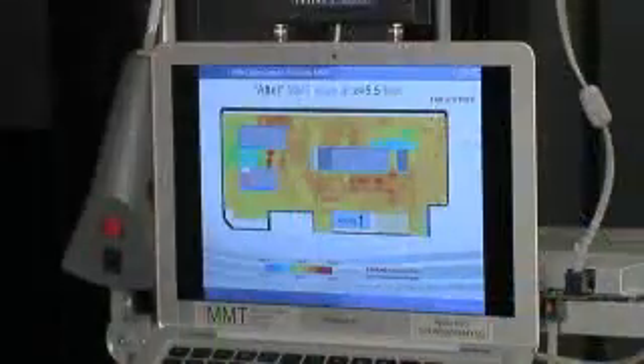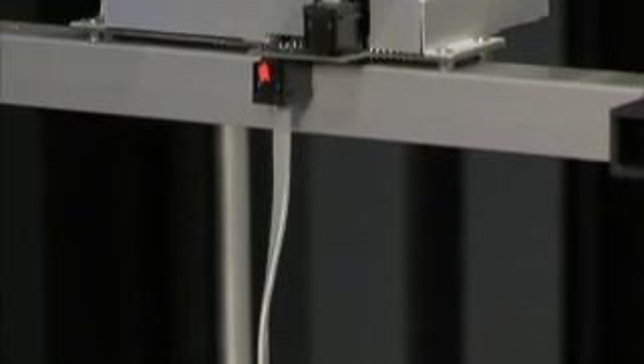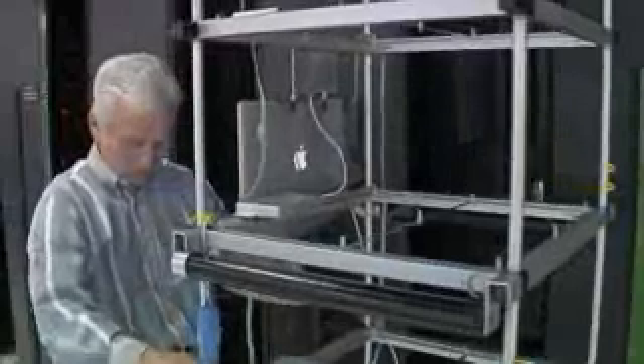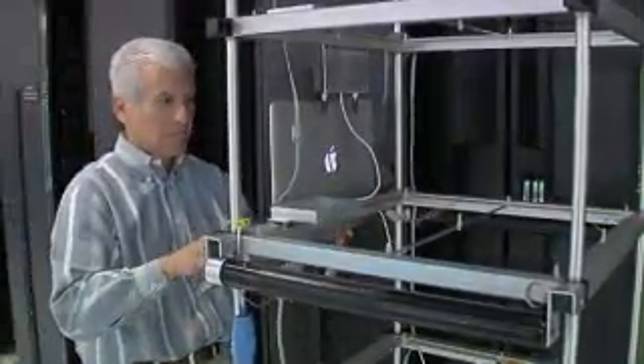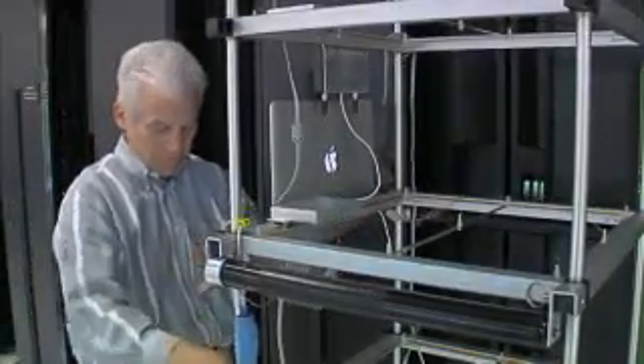The first step is really to determine where the problem areas are in the data center. So we used a tool that was developed by the research division a couple years ago called MMT, Mobile Measurement Technology Tool. And what it does, it basically profiles the data center from a temperature standpoint. Each level of the tool has temperature probes. They have over 100 temperature probes on this tool. So as we roll it around, we get temperatures at each tile placement throughout the data center, and from that temperature profile that we create at post-processing, we can determine where the problems are in the data center.